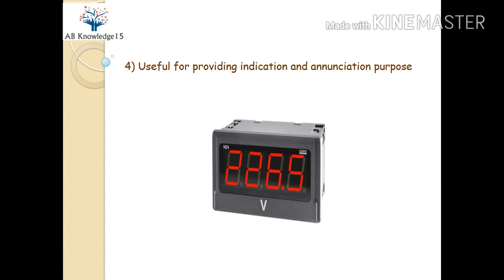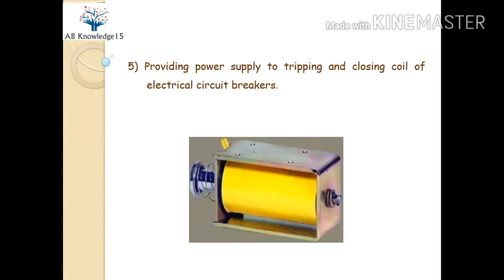The fourth use is for providing indication and annunciation purposes. DC power supply from the battery bank is useful in indication and annunciation systems. The fifth use is providing power supply to the tripping and closing coils of electrical circuit breakers. Electrical circuit breakers are used for control of the plant — for switching on and off motors, transformers, and feeders. DC power from the battery bank can be used for this purpose in case AC power has failed, allowing you to make switching operations as per requirement.